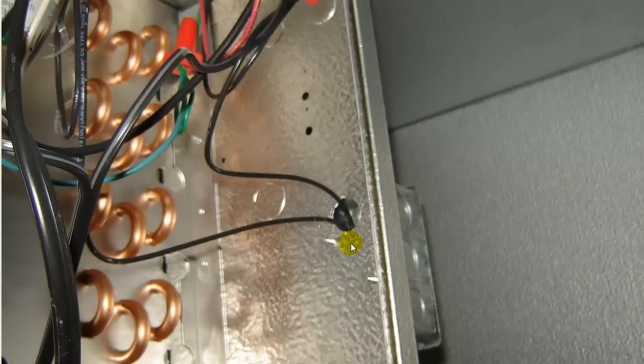This is of course improper. A chase nipple should have been installed there, at least in this case, a plastic snap-in bushing.